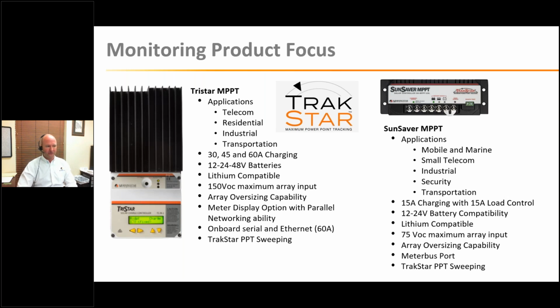A unique feature of these products is the ability to oversize the array, meaning you can put a substantially larger amount of power on the controller than it's rated for, and it will clip that and run at full power with a straight 60 amp output continuously. It's sized much like grid tie inverters with their DC to AC ratios, and now you can take advantage of that off-grid. It's an extremely beneficial feature we're proud of, because we tightly control that power and won't trip the output circuit breaker or fuse due to this regulation. This is a feature on all of Morningstar's MPPT controllers.